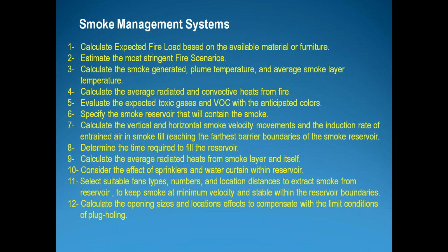Does this building need smoke evacuation or not? If it's stated by the laws and the local codes, then it's okay. But some projects do not need that, and we are spending a lot of money on something that could be solved naturally. And to be clear, if you want to do it naturally, you have to follow the performance-based design, because you have to consider the prevailing winds and the direction of wind and where the air will enter the building and how it will scavenge the smoke outside the building, all this naturally, by stack effect or by buoyancy effect, whatever it is. But this is normally carried out using CFD or a numerical solution.